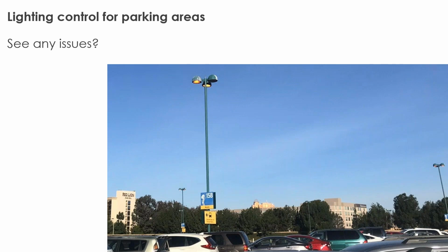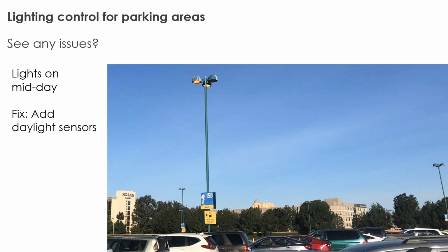In this second example, this is the Disneyland parking lot in Anaheim, California. The lights are on. In fact, one of them appears to be burnt out. But there's ample daylighting, and I don't need to have those lights on because the parking lot is fully illuminated. So a way to fix this would be to add daylight sensors, which you don't necessarily need the Limelight system to do. So let's get into a few examples where you really truly need something different besides simple sensors on your fixtures.